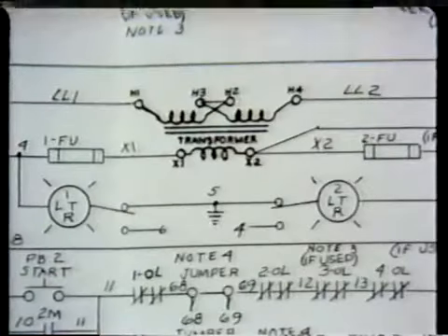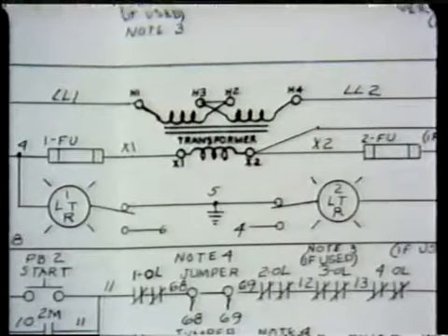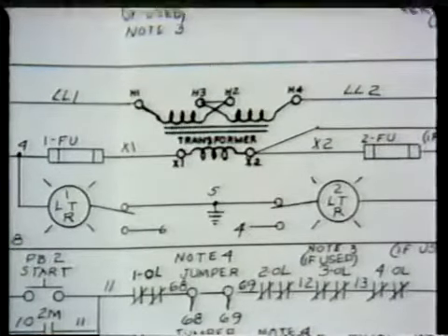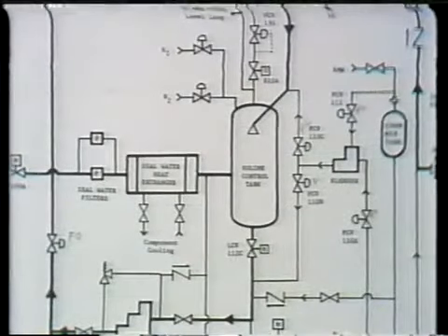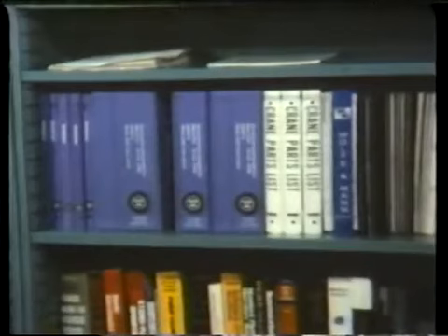Now, there are a number of sources that will provide the information for a safe tag-out. The plant's electrical prints will tell you how to tag out the machine electrically. For the mechanical tags, go to your plant's system prints and the manufacturer's manual. The drawings must be used to ensure an accurate tag-out.